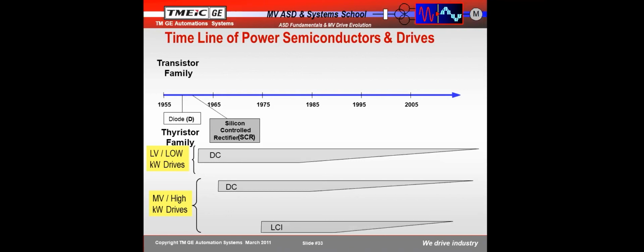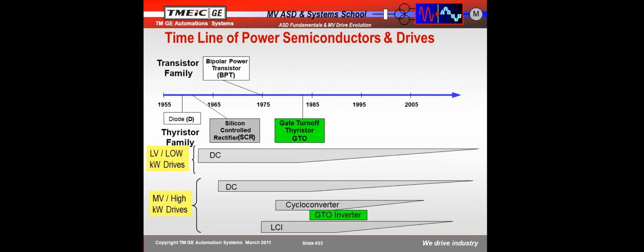Now, the load commutated inverters there on the bottom, that used SCRs, but we required synchronous motors with that. About 1975, bipolar transistors came out, and they were really cool because a bipolar transistor you can turn on and you can turn it off. But we didn't really use it in large devices because it was not available in high voltages and in high current ratings. Well, then we came out with the gate turn-off thyristor.